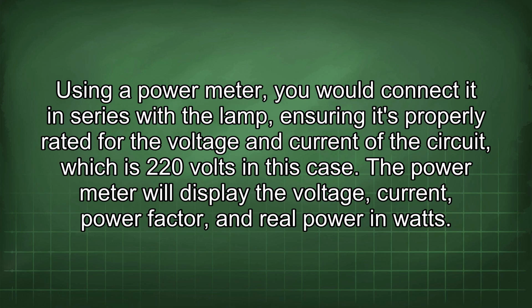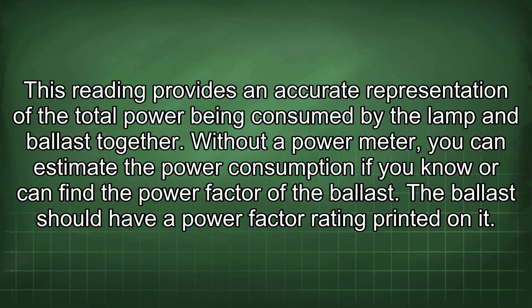Using a power meter, you would connect it in series with the lamp, ensuring it's properly rated for the voltage and current of the circuit, which is 220 volts in this case. The power meter will display the voltage, current, power factor, and real power in watts. This reading provides an accurate representation of the total power being consumed by the lamp and ballast together.